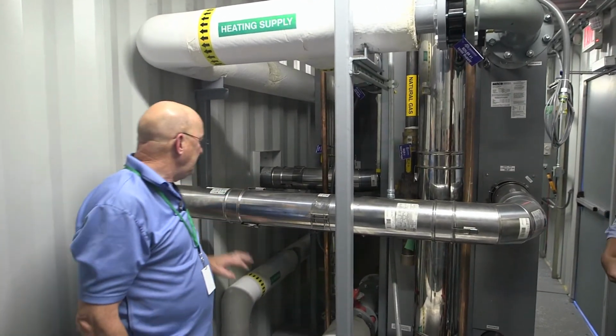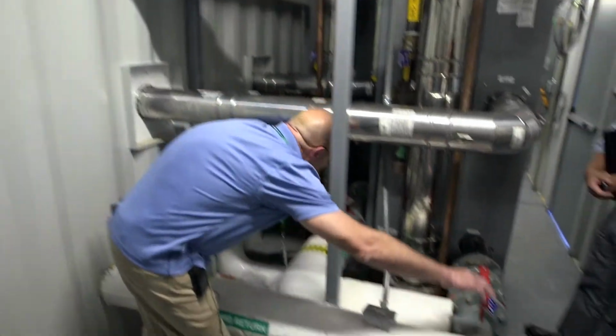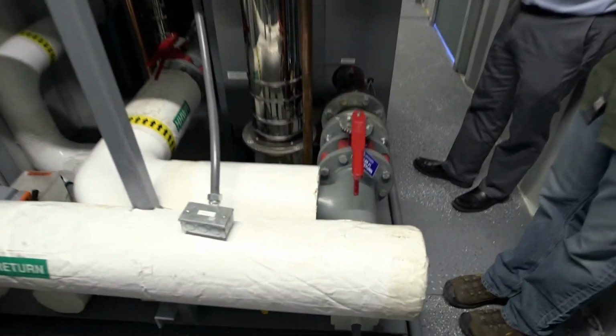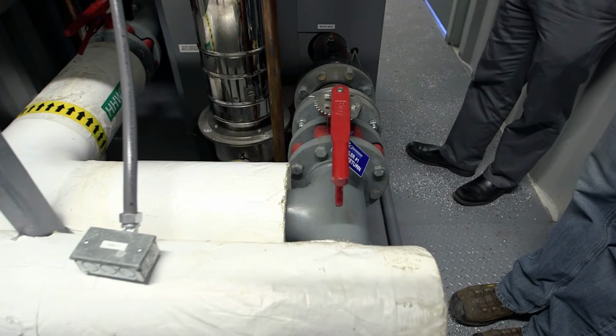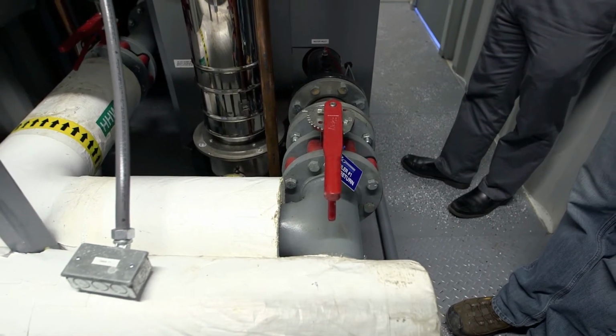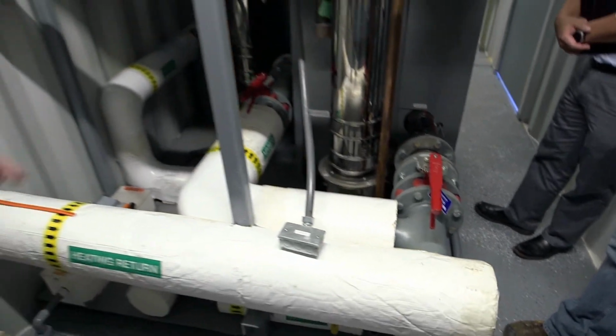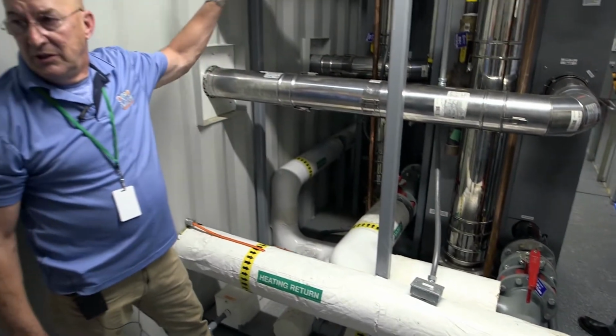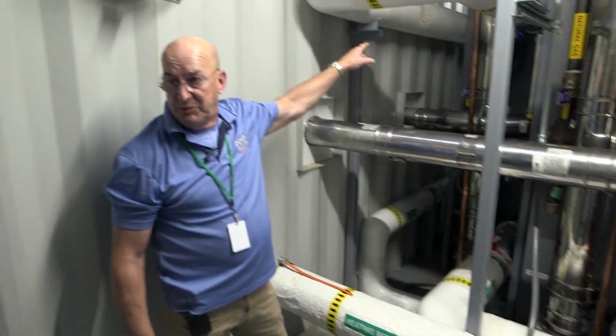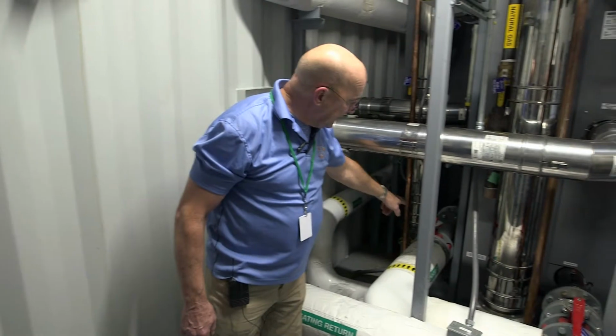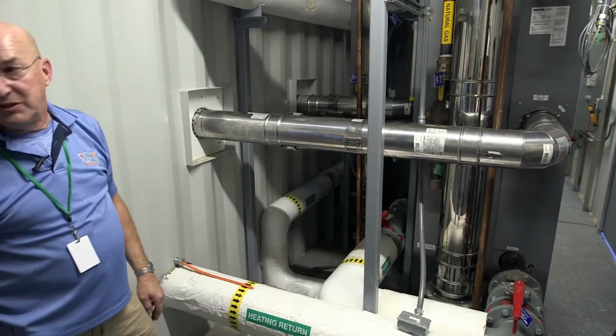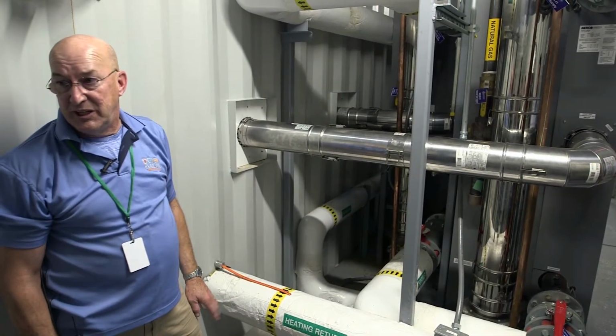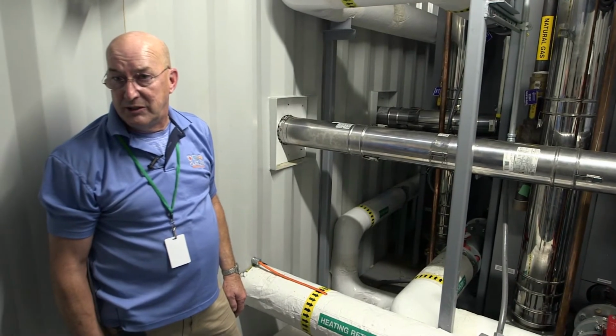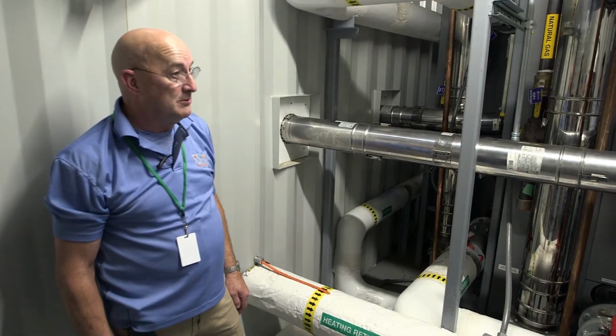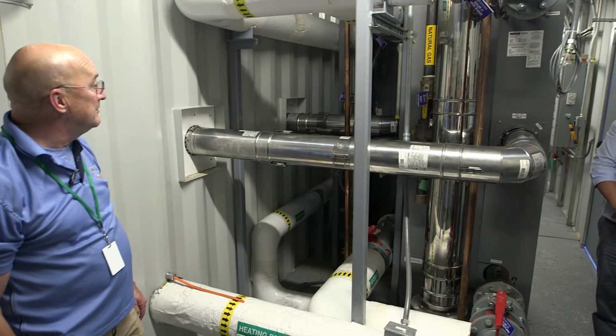All right? These valves here, okay, these are your return water for the system. Once you shut those down, that's it for the return. So if you want to isolate the whole building, the two supply valves over there by the pumps, and these two valves here, okay, you shut it down. The whole system's down. They're not getting any water in the building at all, to any of the radiators or any of the heat piping. That's your safety factor there. Okay?